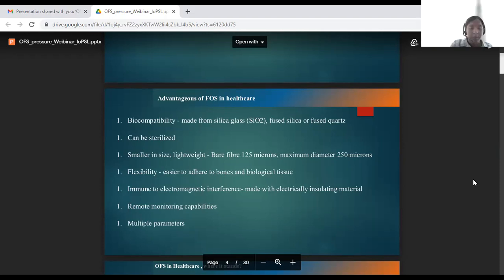Another attractive characteristic of fiber optic sensors is that they are lightweight and flexible, along with their small diameter, which allows them to be used in minimally invasive biomedical applications, for example, in catheters or endoscopic tools. Typically the diameter of a bare single mode optical fiber is about 125 microns. However, with the necessary fiber protection coatings, jackets and polyacrylate coatings, it can go up to a 250 micron diameter. They are also easier to adhere to bones and biological tissues, and therefore fiber optic sensors have been developed to measure the deformation of bone due to strain in certain research studies.